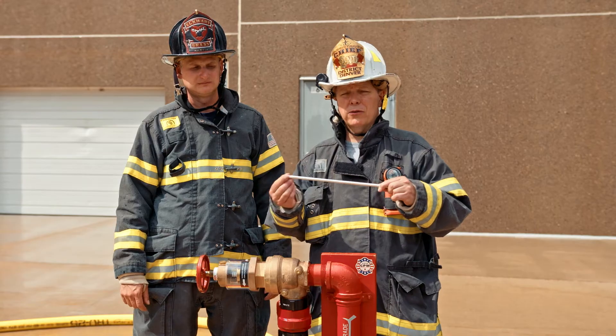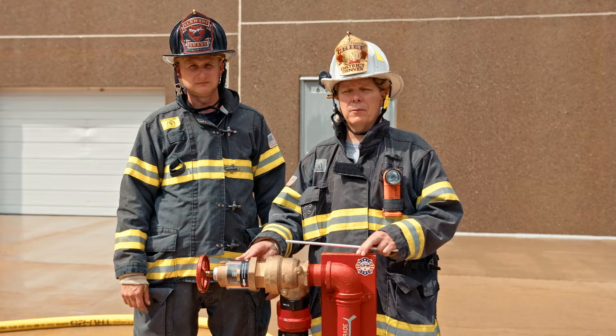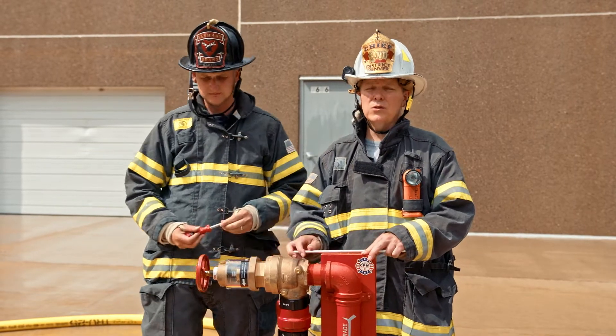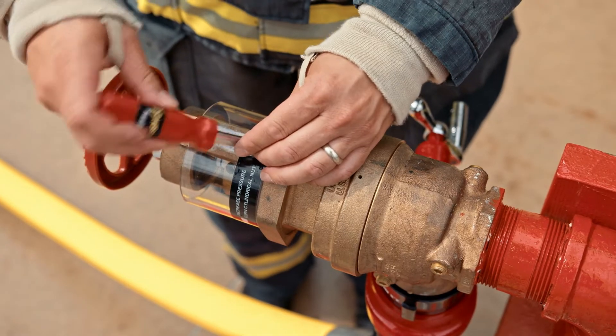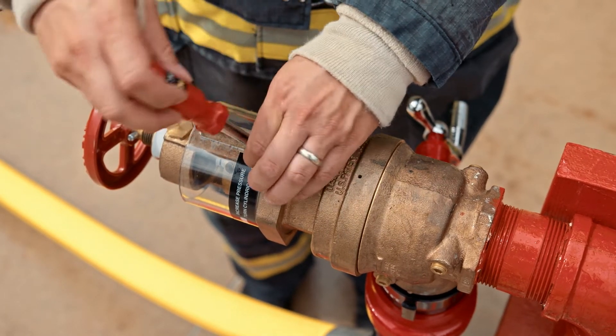Using this adjustment rod, 3/8 inch in diameter, we can easily access the rotating barrel to make the adjustment. Chris will take that protective shroud off at this time using that pin and hex driver. If that's not available, you can break that protective shroud off by attacking the weak points.